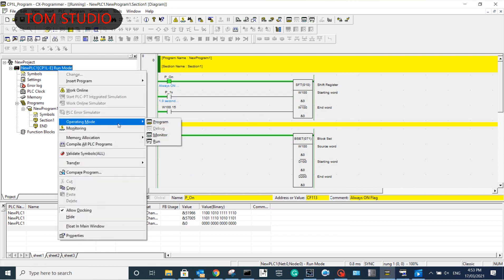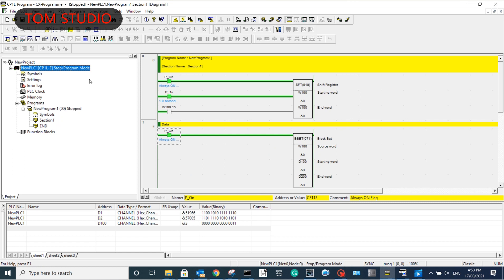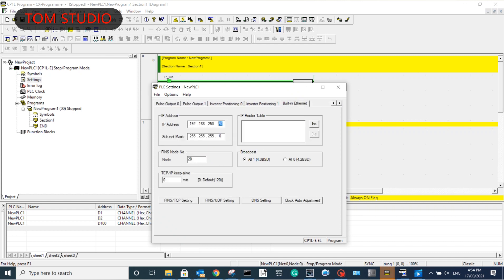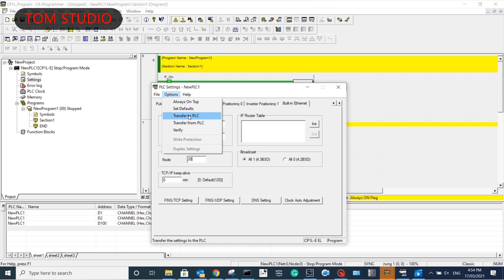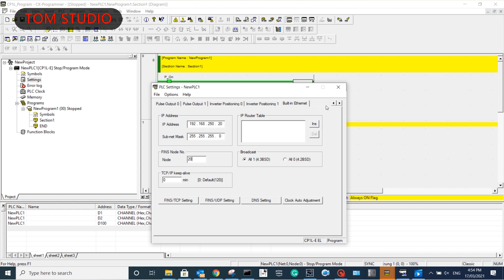Just set up the IP address in the PLC settings and set up the node number. Please be aware that the node address must be the same as the last digit of the PLC IP address. For the NXFINS function block, it is necessary to set up the PLC network number. If you don't set it up, the default PLC network number is zero. Please note that it is necessary to cycle the power for the CP1L PLC to make the settings take effect.